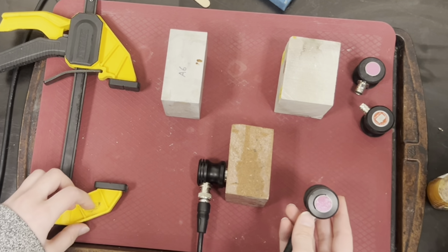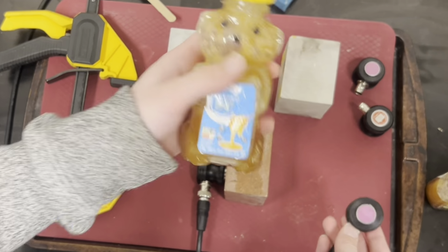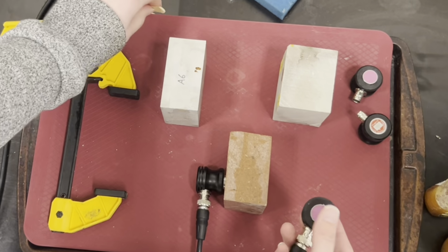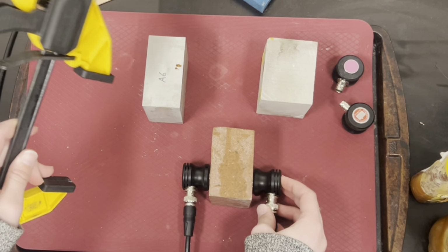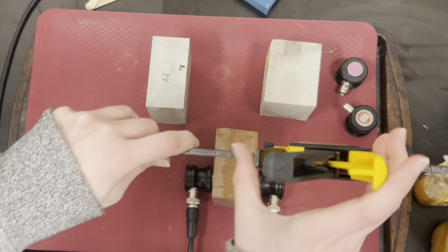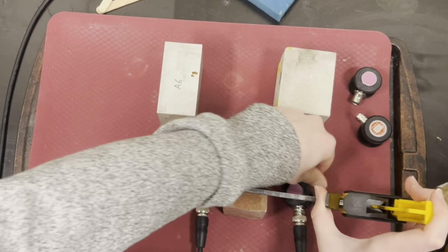And if you need them to adhere to the surface of the rock, you can use honey and put some honey on the surface of your transducer. And then once you have that done, you can place the transducers like so, and then you can get your clamp here, and you can...